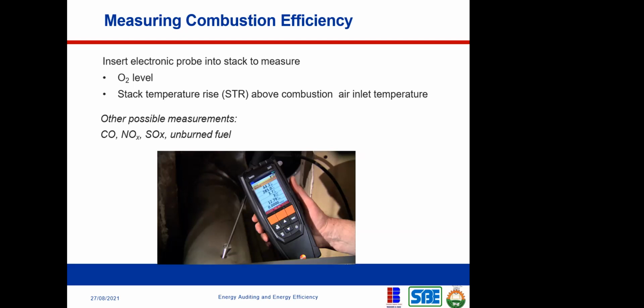The probe will analyze that exhaust gas. It will check if there is carbon monoxide. If there's carbon monoxide, it means that the combustion is not complete. It will check the NOx or the SOx, right? Now, the presence of these gases is an indicator that there is unburned fuel in your stack gas. That's what it means.